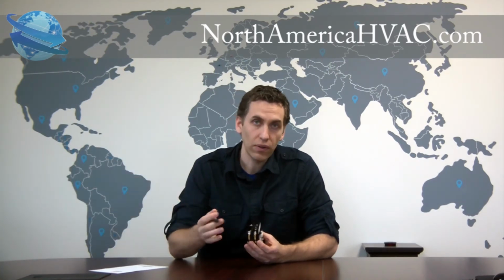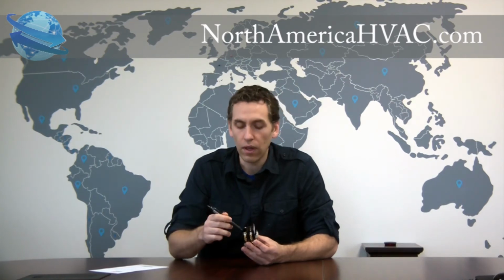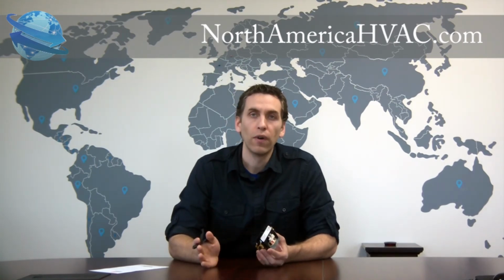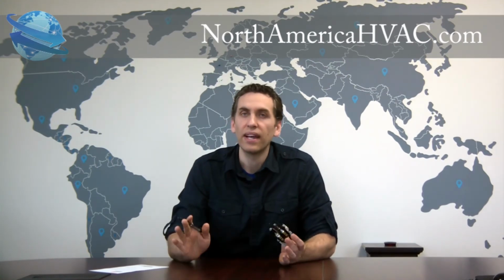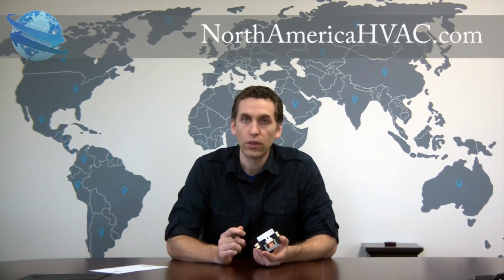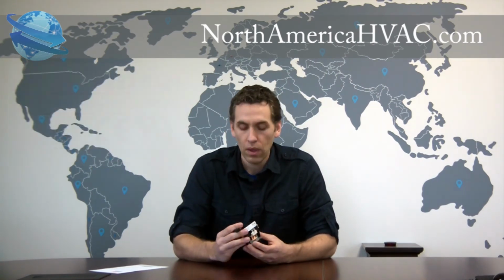In your AC condenser in a residential unit, you're going to be looking at a load voltage of 220 volts passing through the top. So while you can change the load voltage, the coil voltage you cannot change. You need to stick with what the manufacturer recommended. It's very specific. So you look at your label and you'll see this one says 24 VAC for the coil voltage, and you need to stick with that.